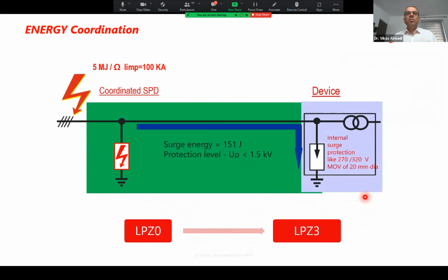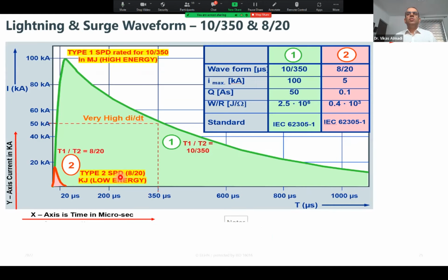When we talk about this topic, not only the voltage, as I mentioned, the current also is flowing through the equipment when the voltage is there. So voltage, current, and the time of flow of this current all matter, and it should not exceed 151 joule. You remember 151 joule is the rating of those MOVs. So if the 151 joule figure is exceeded, even though the voltage is the same, your system will still fail. So we have to see carefully what arrestor we are using here. It is not a showpiece, it is something which actually protects the equipment at the end. Final aim is achieved. This part is already known to you, so not to repeat it again, but I would like to show you one video here where it will differentiate between the two waves very clearly, because it is very important to understand 10/350 and 8/20.